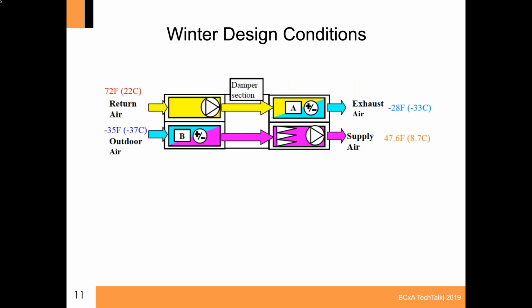So basically, our design conditions for winter are that we're bringing in 72 Fahrenheit or 22 Celsius return air. We are capturing heat recovery off the core and supplying that at about 47.6 Fahrenheit or 8.7 Celsius. And I'll show you some snapshots from the building automation system from when we were doing this that actually show what we were getting off of that core.